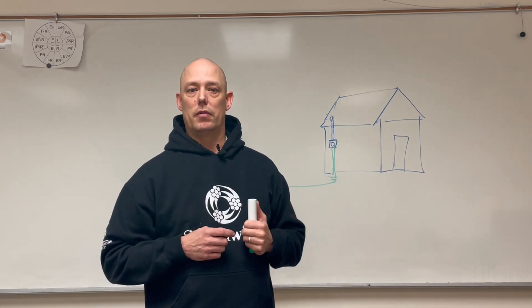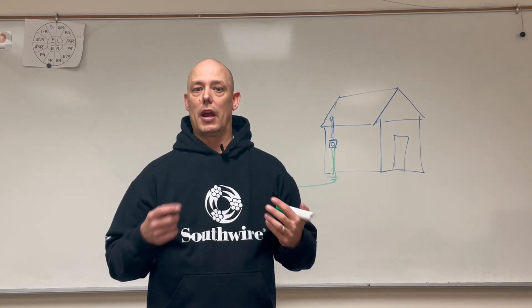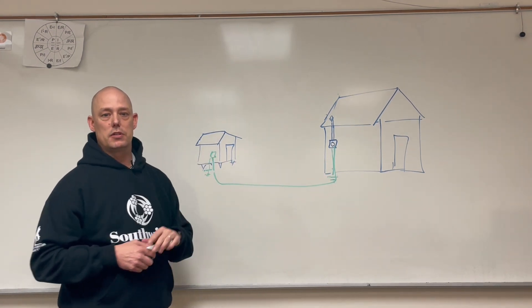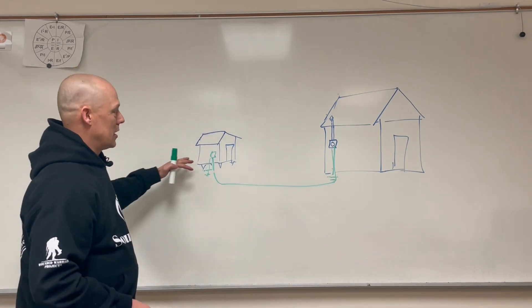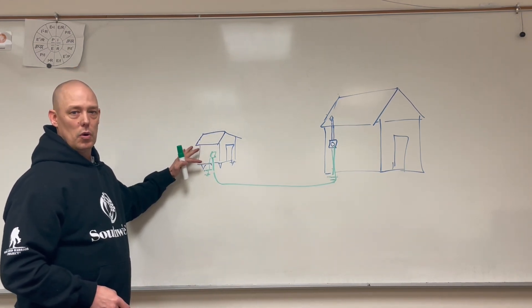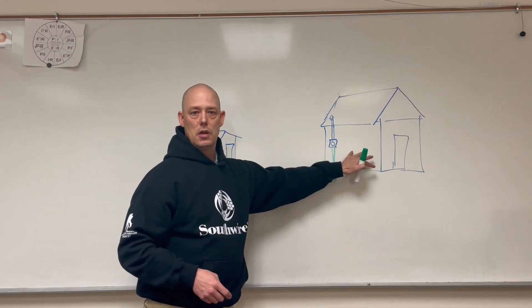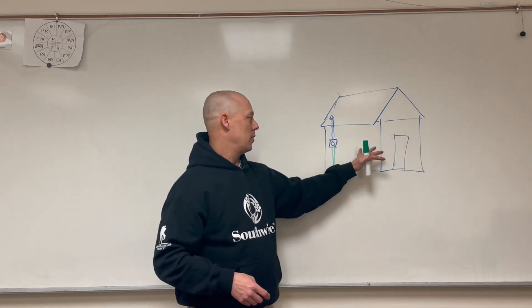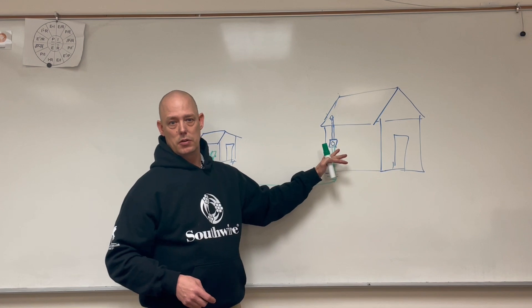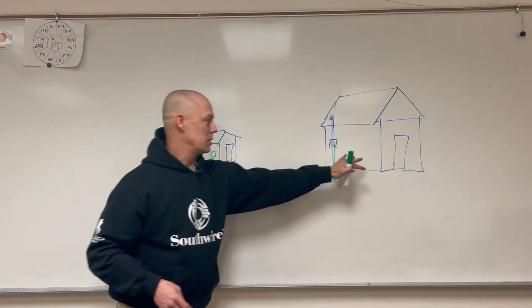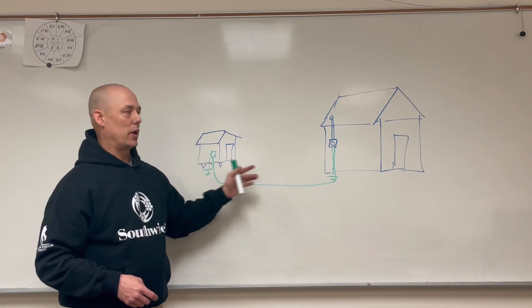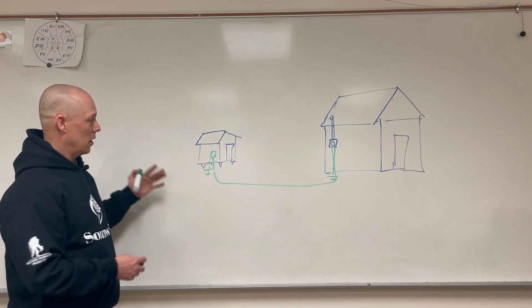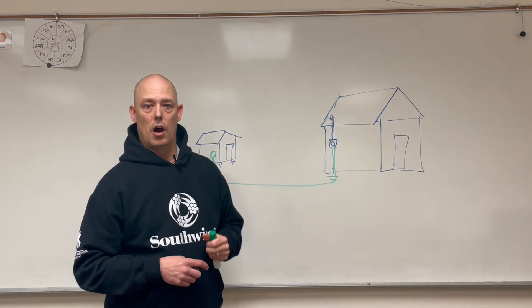We want to be able to trip every breaker for protection and protect this building, so we need that equipment ground going back. What we don't want is a bunch of circuits coming from the house to feed the shed with no way to turn it off — maybe it's fed from a subpanel inside instead of the meter socket, and there would be no way to turn off that breaker if the house is closed.